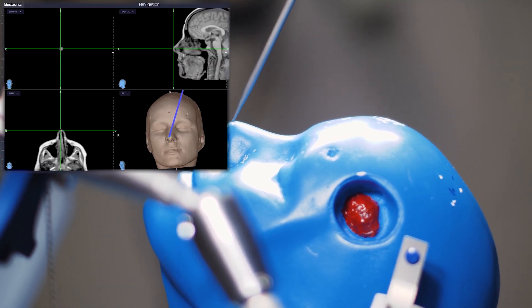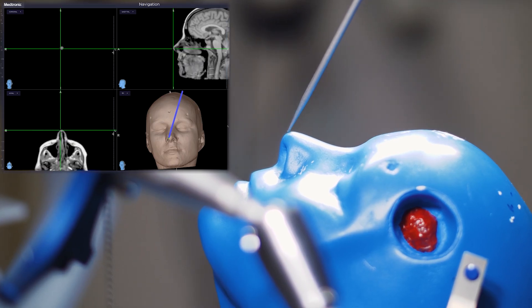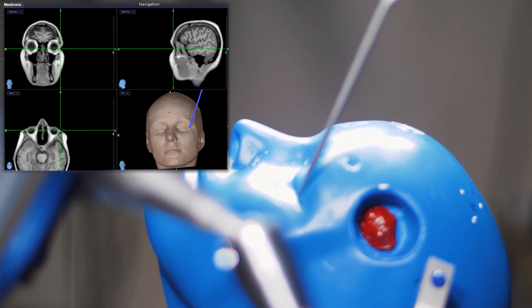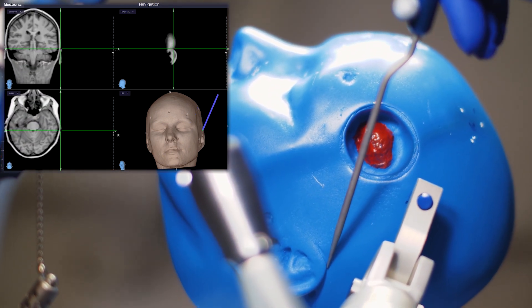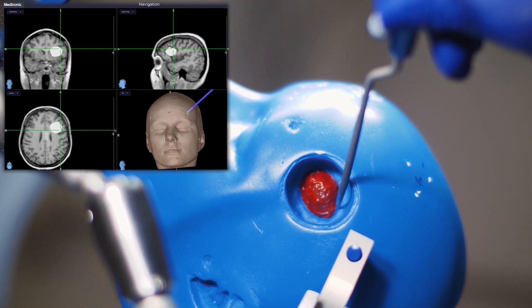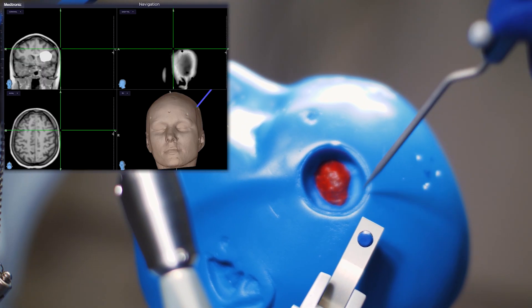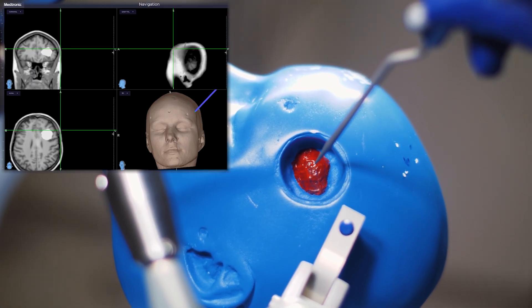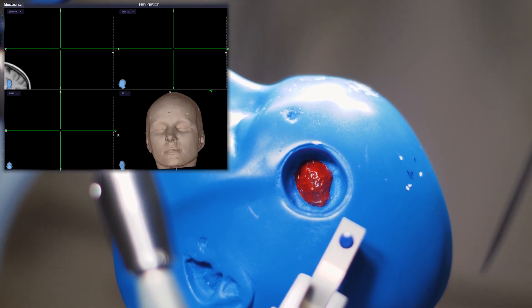We're going to touch the tip of the nose on the model and you can see in the MRI that that correlates well. Let's look at the inner part of the eye — that looks good — the outer part of the eye and the tip of the ear. This is all looking like it's corresponding really nicely. If we put the pointer into this pre-made hole, we're on the tumour. This is a pre-made craniotomy, or trap door in the skull, that's going to allow us to access the tumour straight away.